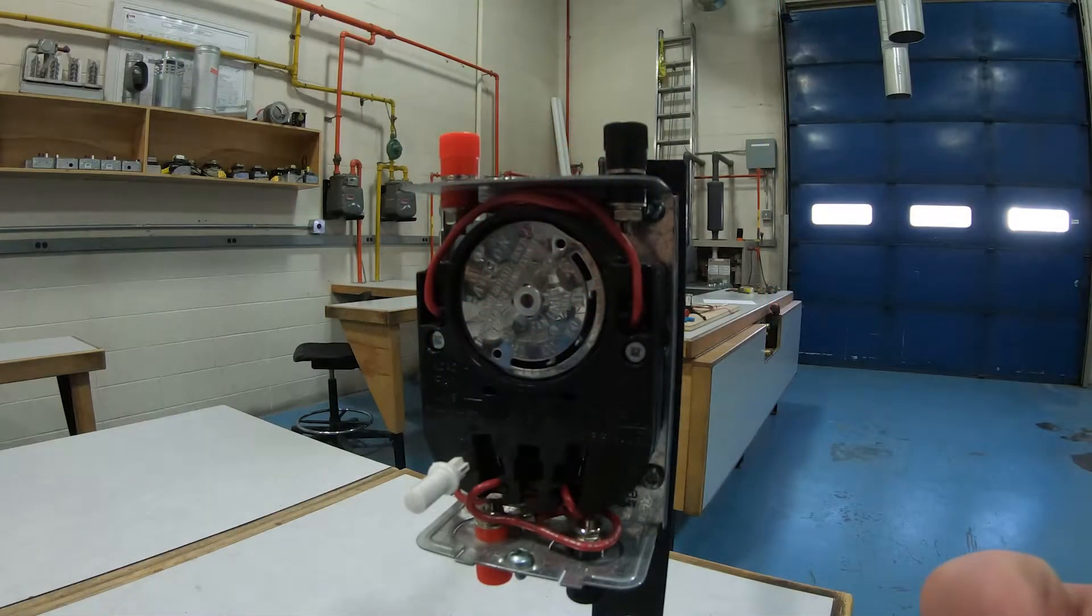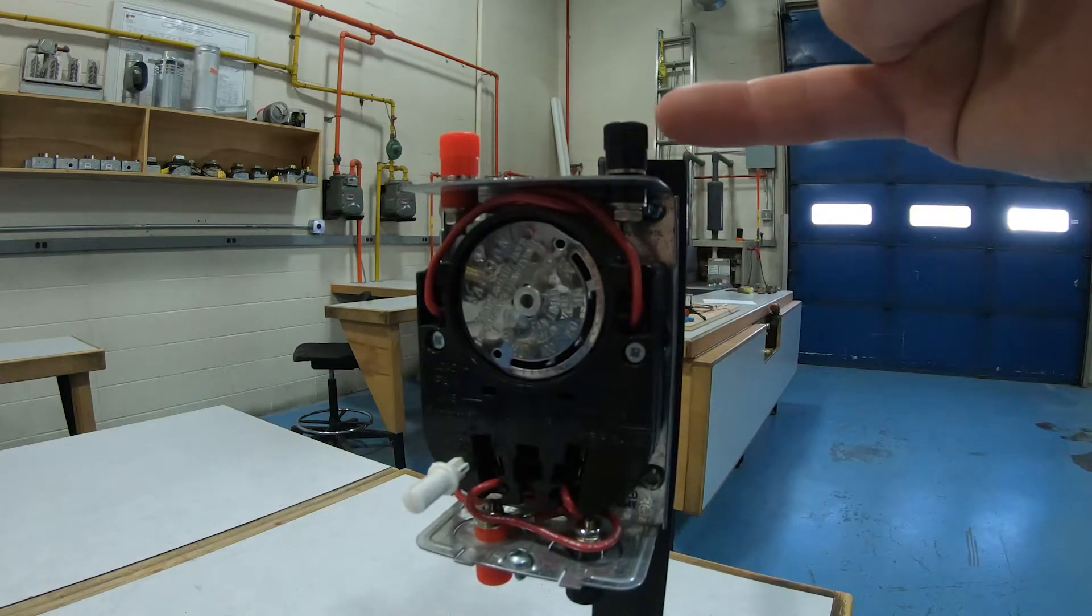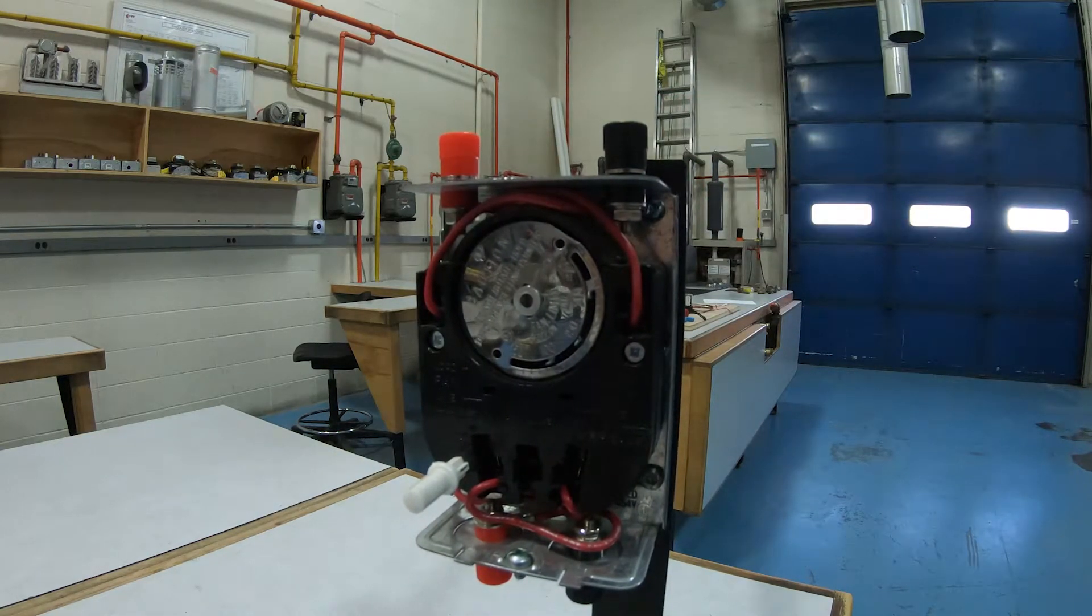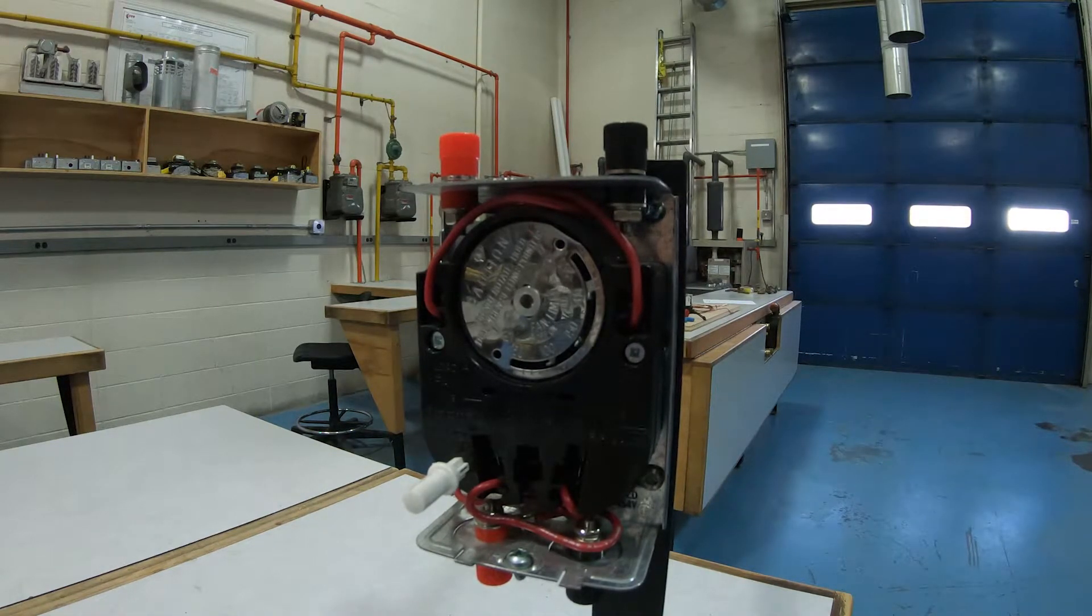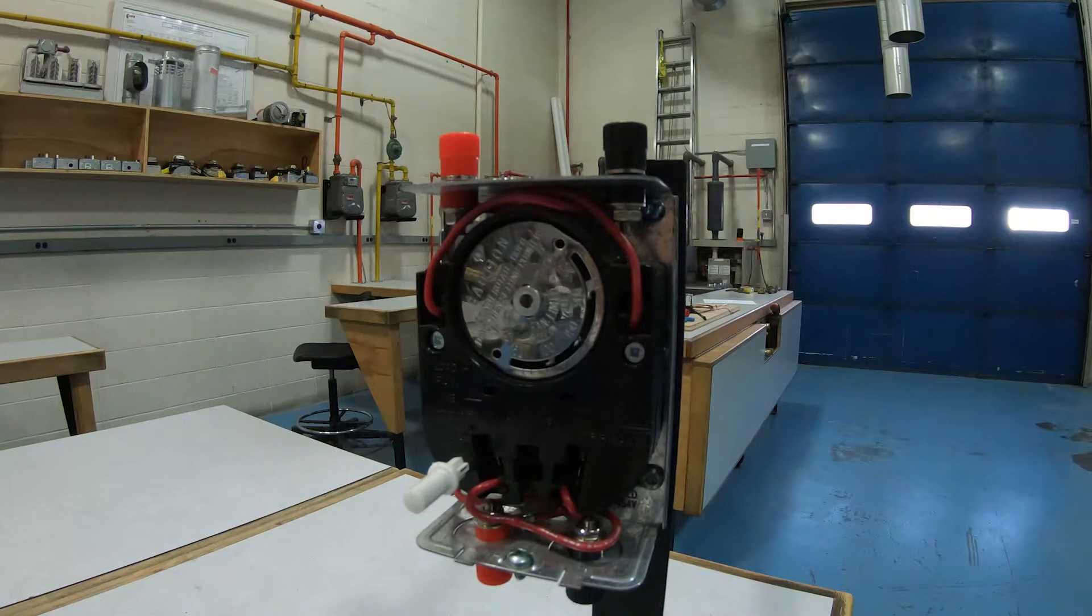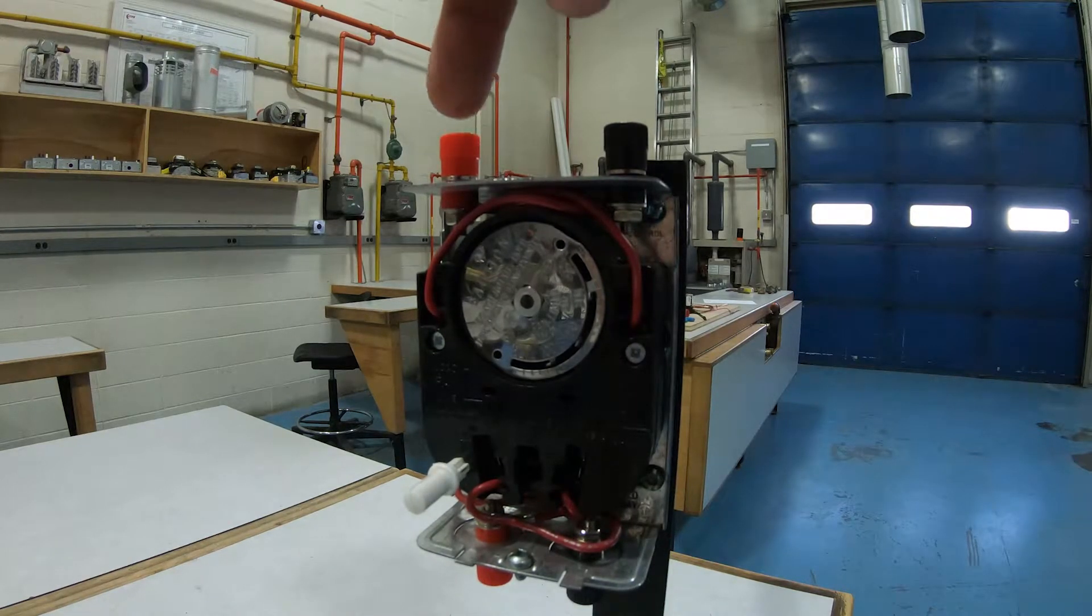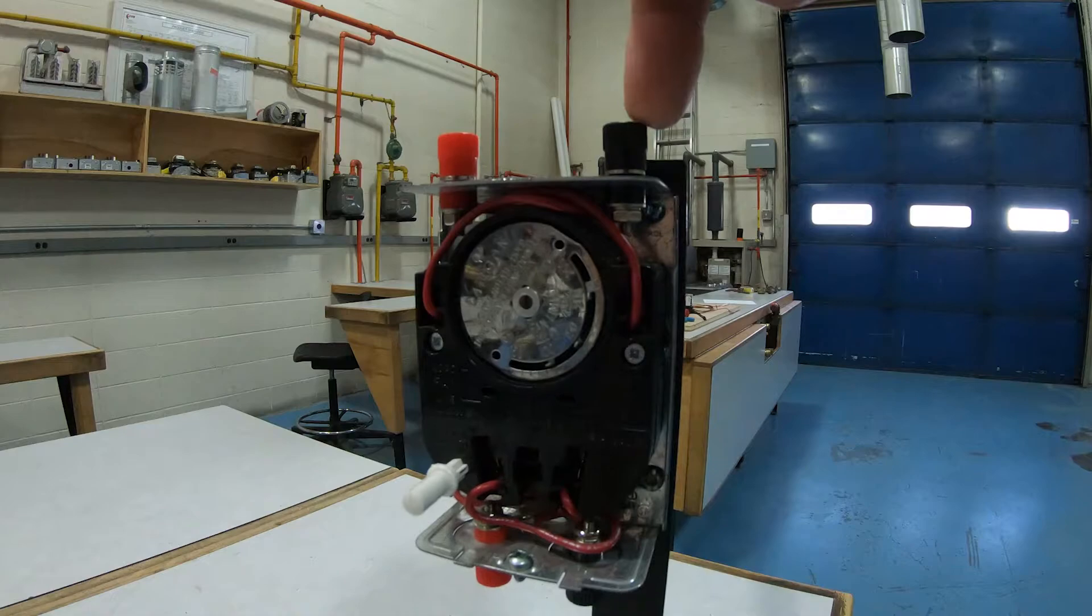The limit, though, measures the high temperature inside the heat exchanger. If it gets too hot, it'll shut the burner off. So power comes up through here, out through this side right here, which has terminals coming out, and that will control somehow the gas valve. It'll either turn off the 24 volt transformer or it'll be directly wired in with the gas valve with 24 volts, one or the other. But fan side, safety side for high temperature.